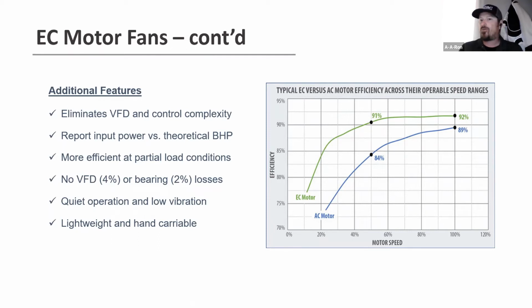And as we slow those down through voltage and not hertz, our efficiency stays over about 75, 80% across its whole power band. So we're quieter, we don't have any vibrations that transmit back to the system, and everything is hand carryable and lightweight. We also talk about horsepower. Most of these fans are always rated in kilowatts, so we're actually talking about input power versus just rated power. Where you may see a 10 horsepower motor in a system, we'll end up supplying something that equates to about maybe a 6.5 horsepower motor, but we tend to operate probably below that unless we're running right at peak efficiency.